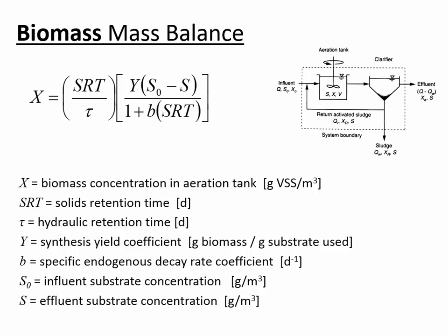Well, what we're going to be measuring as the biomass is the volatile suspended solids. Now, there's total suspended solids and volatile suspended solids, and what we're assuming at this point is that anything that's volatile inside of the aeration basin is biomass, whether it's living or dead. So you were wondering about the units, right? Anything that's volatile, and remember that's if we put it into a furnace and it cooks off at 550 degrees Celsius, we assume that it's either a living or a dead cell.